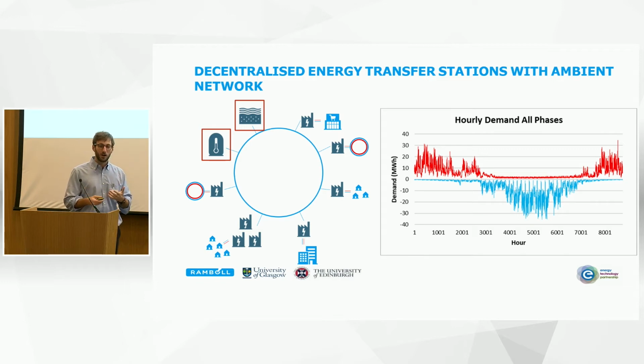That's where balancing units come into play: an active balancing unit, such as a heat pump, or a passive balancing unit, such as a thermal energy storage system, usually a seasonal one. This could be an aquifer with a hot and cold well, where we can shift that profile and use it during winter or summer. There are a lot of issues with this as well, but it's an idea on how we can start introducing that simultaneous aspect more and more.